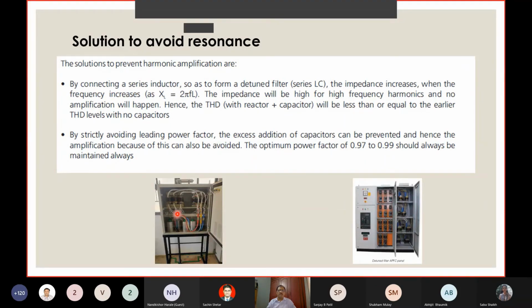Even here, as you notice, the reactors are on the top, the capacitors are placed slightly away from the hot air, and the fan is at the top. This is recommended very strongly as a practice by the panel manufacturers.